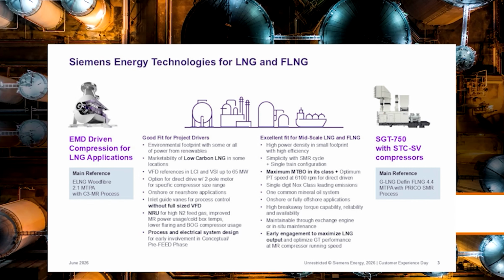So in terms of eLNG versus turbine drive, one of our best references on eLNG is Woodfibre. Currently under construction, it's a 2.1 million ton per annum project in British Columbia, and it uses the C3MR process. So it's entirely motor driven, with a large portion of the power coming from renewable hydropower in that area. So this gives us a very marketable low carbon LNG, and Siemens Energy provided all of the motors and the drives and the electrical equipment along with the compressors. So a pretty interesting reference because it's pushing up into that horsepower class. And we'll talk a little bit more about the process, but it's a good model for other projects which are looking for a low environmental footprint, especially when you have some renewable power available in the area.